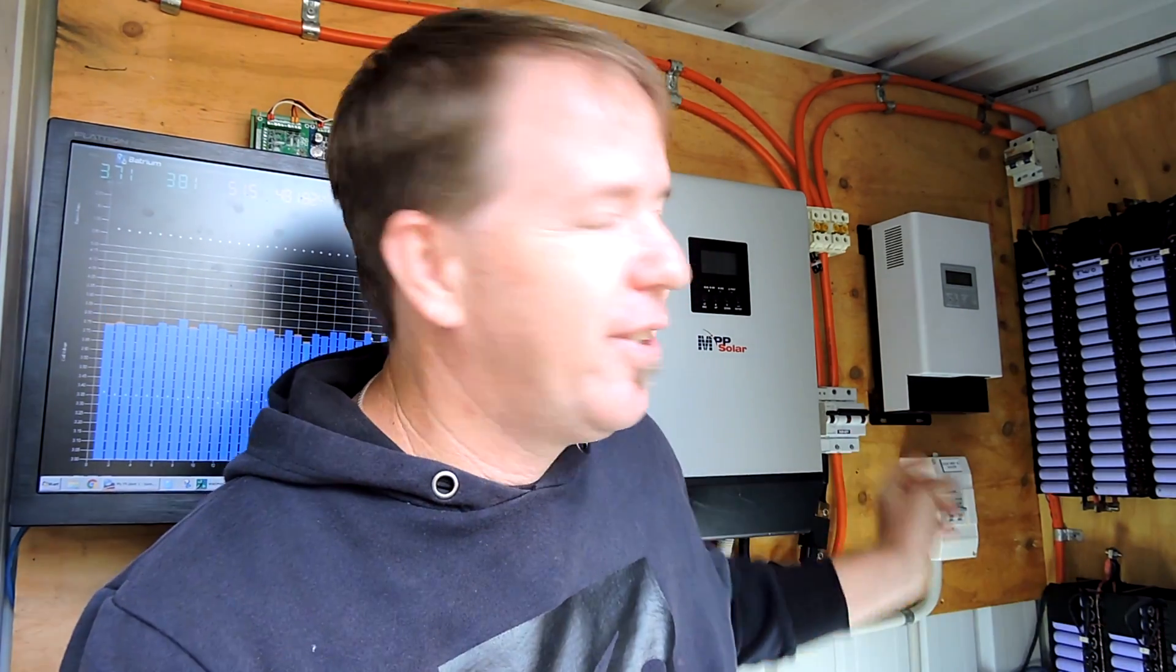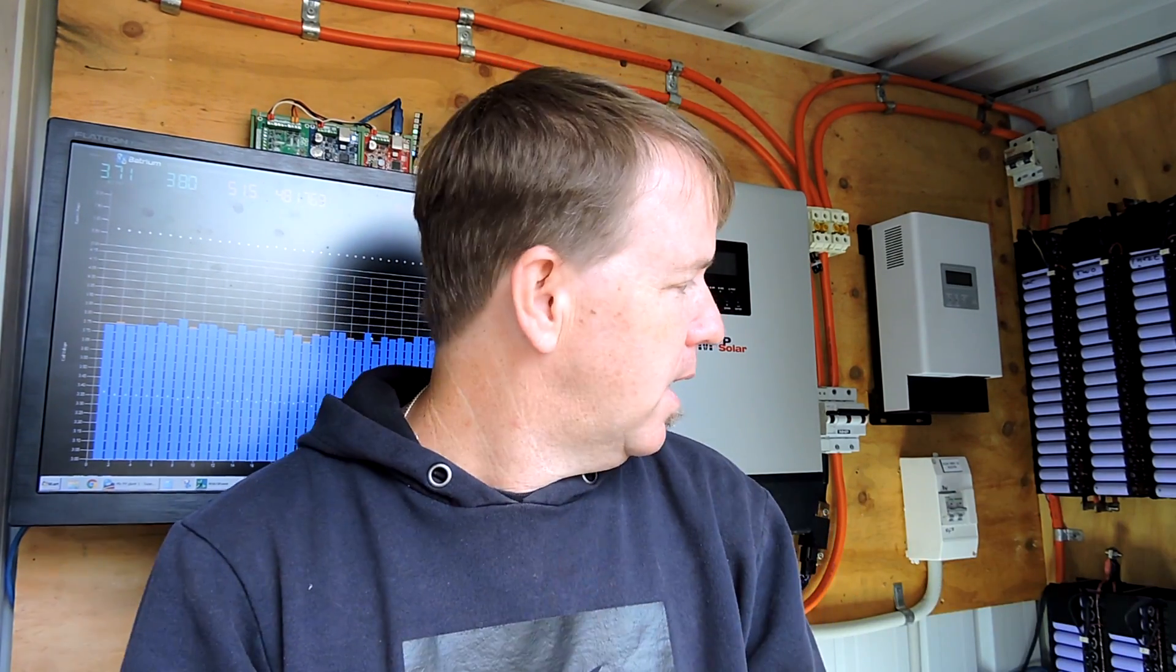It does prove that the shunt trip does work as designed - 55 degrees centigrade and it's got to be there for a minute for it to actually trip, to stop it obviously just tripping for a single one second high temperature event.